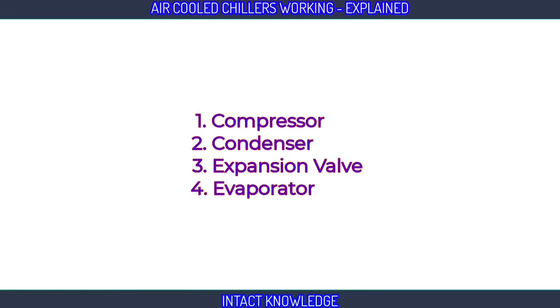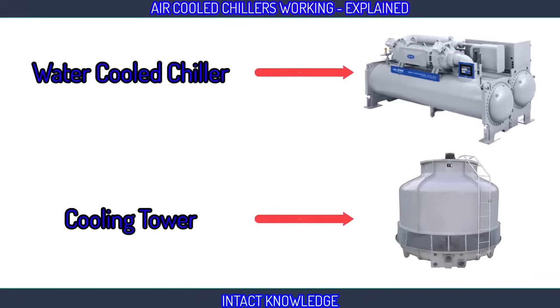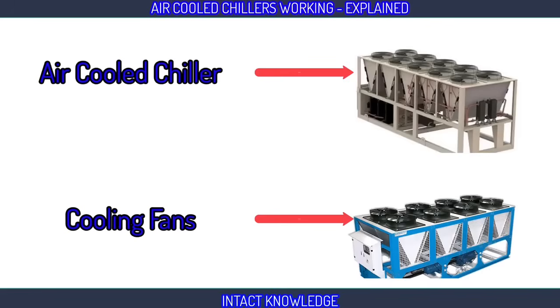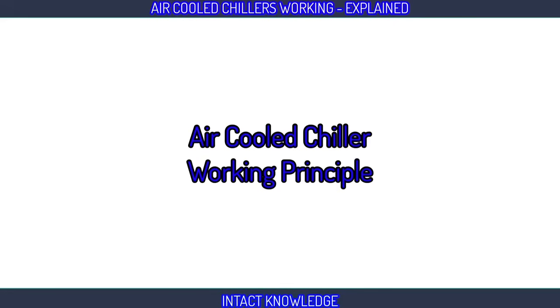Both chillers consist of compressor, condenser, expansion valve, and evaporator. In water-cooled chiller, we use the water from the cooling tower to reduce the temperature of the refrigerant. But in air-cooled chiller, we reduce the temperature of refrigerant by using fan motor. That is the difference between the two. Now, let's see how air-cooled chiller works.